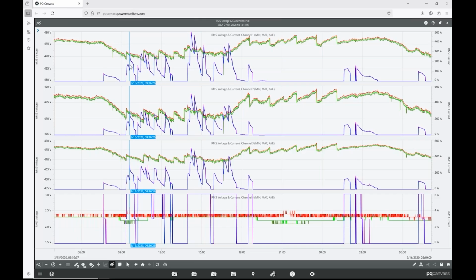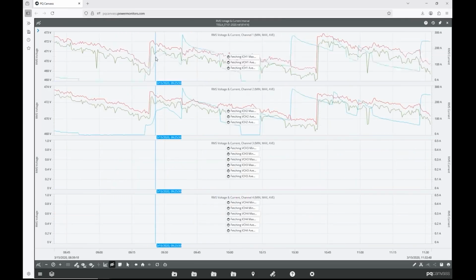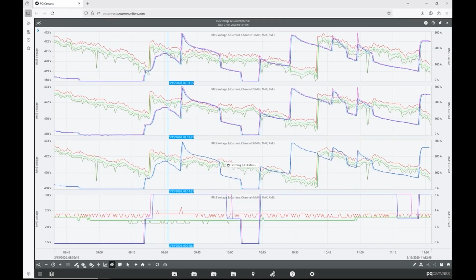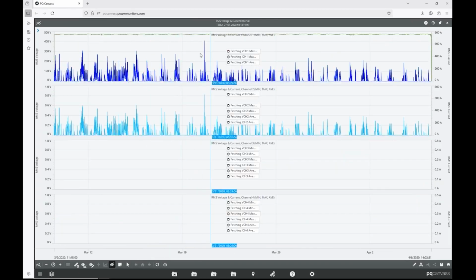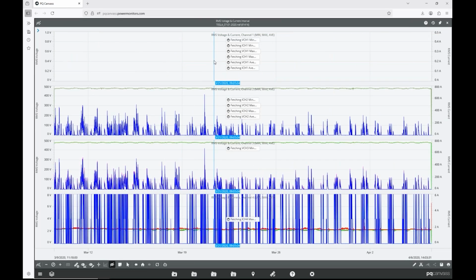And here you can see they stack. As more and more cars pull in, we're seeing the total transformer loads. So you have multiple cars kind of with the current stacked on top of each other. And so you'll see a step increase as a car pulls in and plugs in, and then the current gradually decreases as that car becomes more and more charged, and then another car also plugs in. So that's a step increase in current, and then you have two cars that are now tapering off, and then one car disconnects, and then they step down to zero. And so you see this pattern over and over of a step increase and then a gradual ramp down. So that's the characteristic load pattern of a supercharger or other high-power charging system.